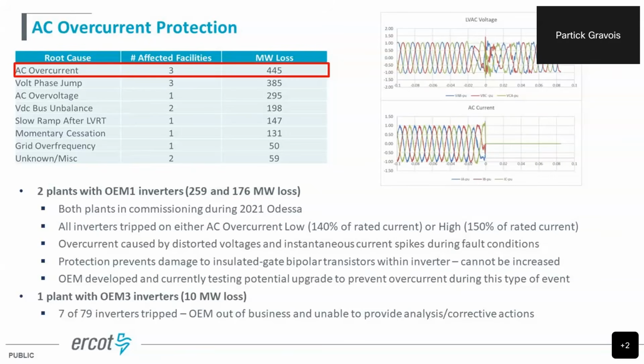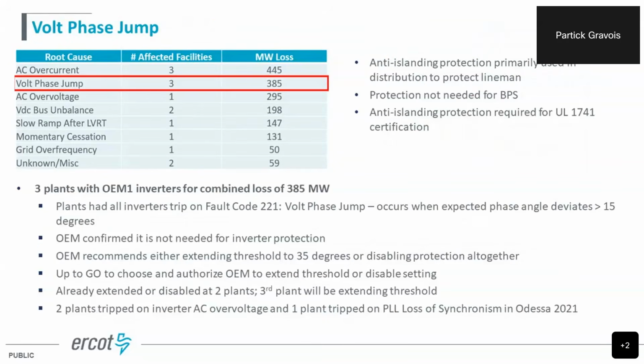We had one other plant with the OEM 3 inverters that only had about 10% of its inverters trip, a 10 megawatt loss. Again, this is the one that's out of business, so we've had difficulty getting corrective actions for this plant. The next is a volt phase jump.